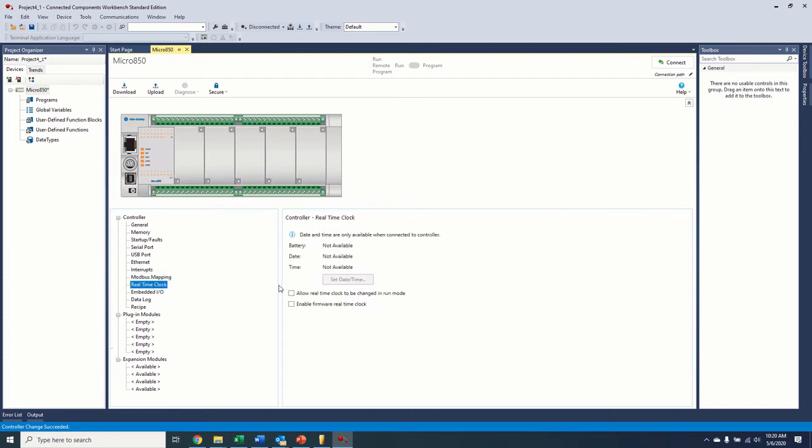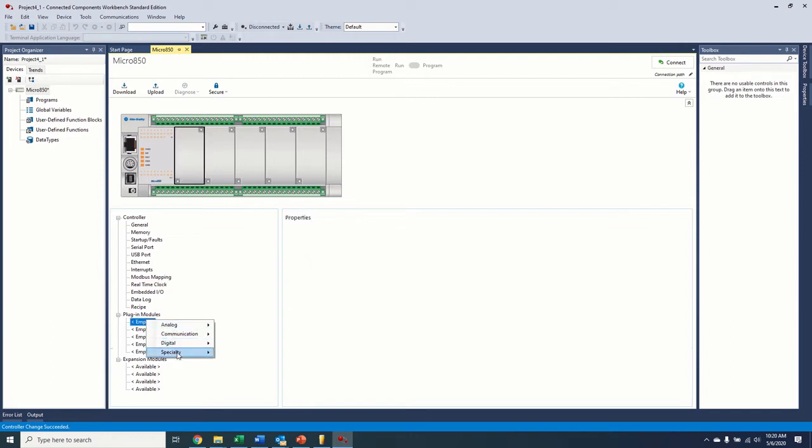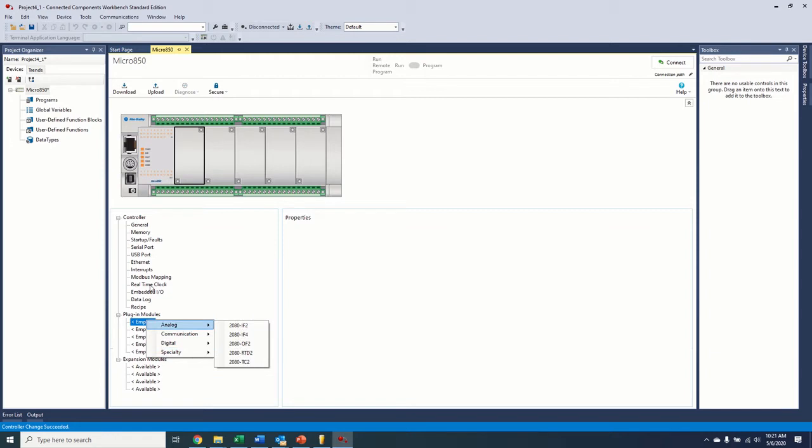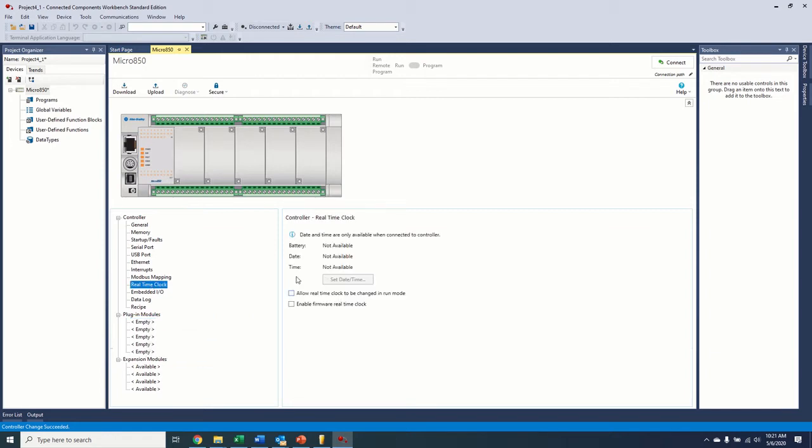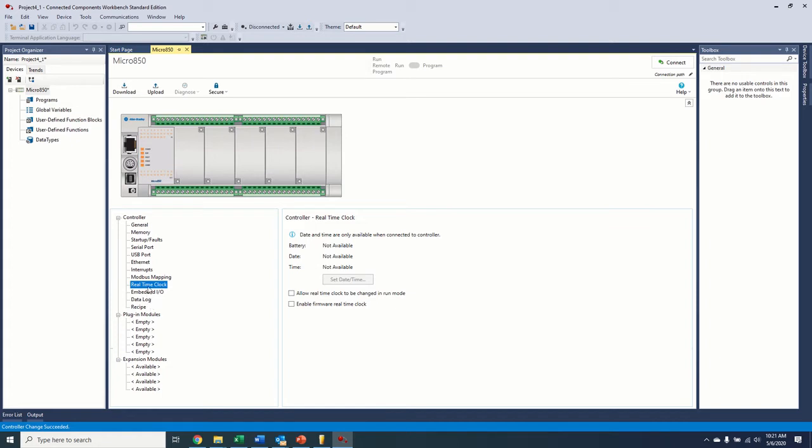The real-time clock, this is available if you have a plug-in module. The plug-in module is called the Memback RTC real-time clock. So this will back up your project as well, so it's a memory card equivalent and a real-time clock. If you're using a Micro820, the Micro820 has a real-time clock inside the controller, so you don't need this module. What this real-time clock menu does is you can enable the firmware to run the real-time clock if that module is, for some reason, disabled, pulled out, broken, stops working. Now, the firmware real-time clock is not going to be as accurate, so this should only be a temporary thing. But if this was an 820, all of this would already be filled in for you. But we don't have that module, so we're not doing that.